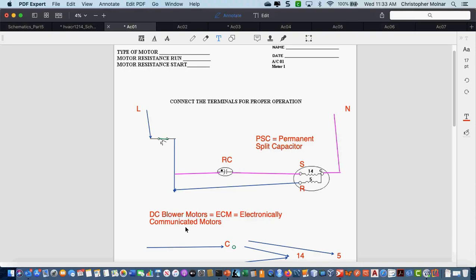The reason for this is that my PSC blower motor, when it's running without much of a load on it, might be taking 4 amps. The same ECM motor might be taking 0.3 amps or 0.6 amps. Okay, so there's a significant power savings with ECM motors, because ECM motors know when they need to run at high speed. The motor itself controls based on the amperage being used, based on how hard it's working, how much power it puts into the motor. We can ramp up and ramp down a DC motor where we cannot do the same thing with an AC motor. Any questions on this? No, sir.